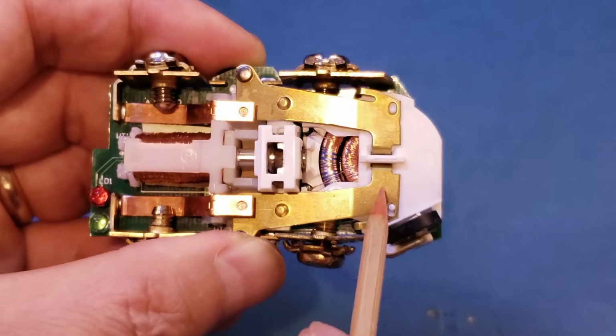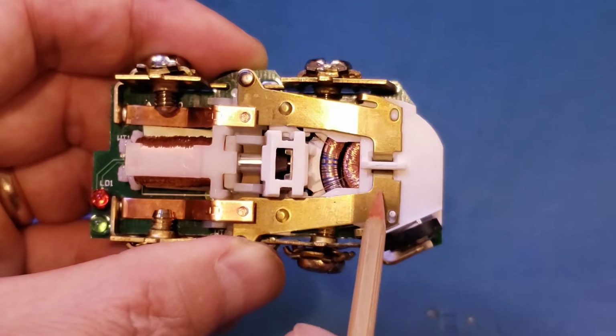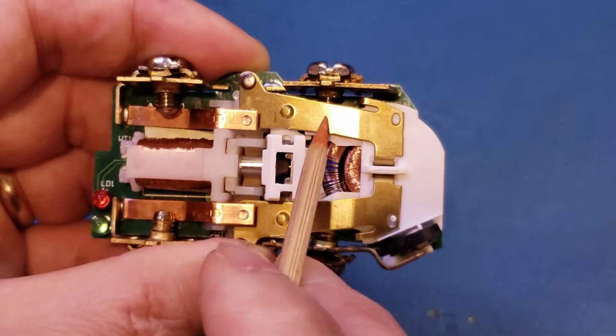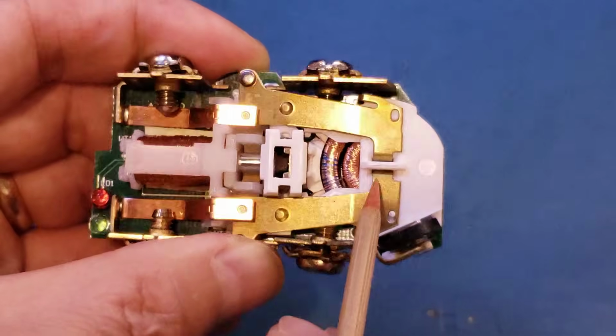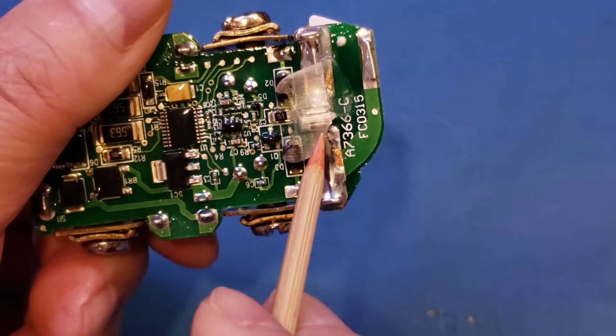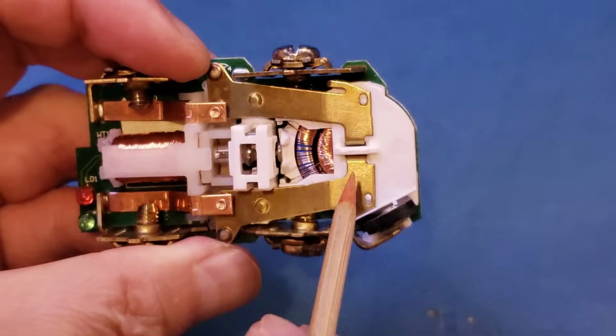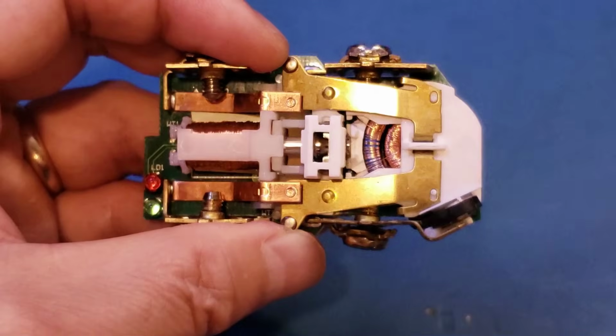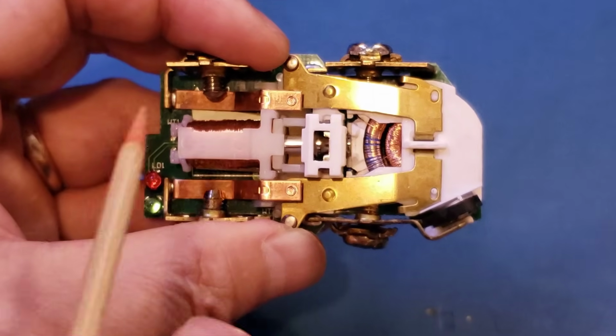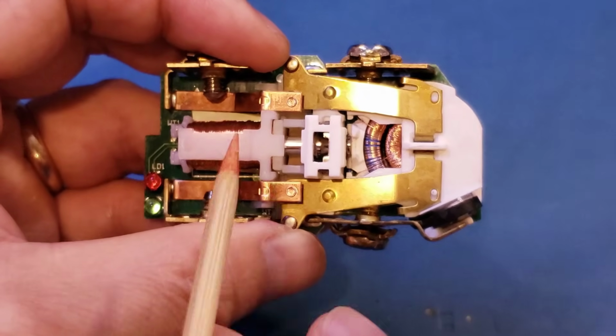As you can see, these sides are the live and neutral, and these two metal strips actually go through the transformer. You can see these come out from the other side. So essentially, they form a single-turn winding. When the circuit is operating normally, the current going through the live and neutral would be exactly the same.